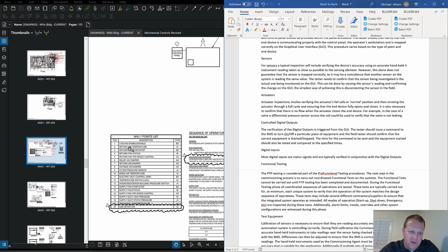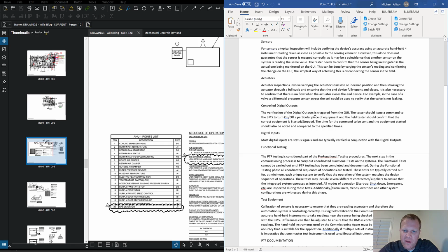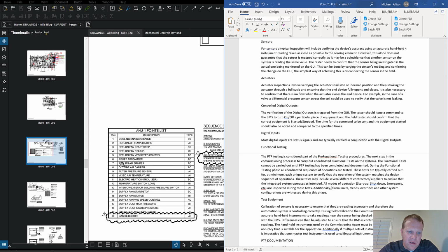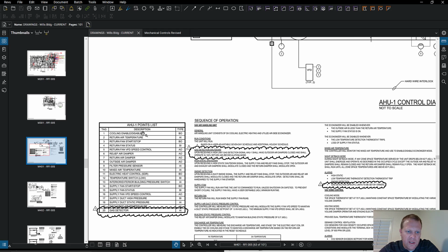And that's what I was trying to show, like, okay, you have a couple temperature sensors here. Do we have the right one? Do we have the right sensor? Are they reading correctly? Are they showing up correctly on the HMI, the human machine interface? Oh, here they're calling it the graphical user interface, whatever. The outputs, so you could have on, off. The cooling enabled, disabled is an output, right? So anything fan start, stop, that's an output. And so you're testing that this output on the controller is actually able to do exactly what it says. Is it able to start and stop the return air fan? Is this button that says it's the return VFD speed control, is it working? Does it have an output?